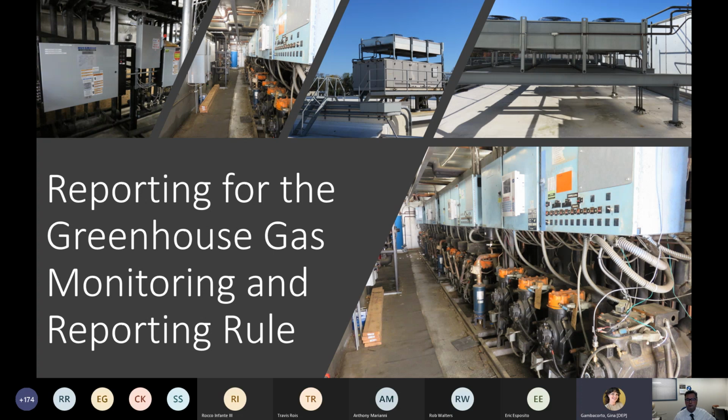Okay, we have one question from Brian Desselfin. He says, our HVAC contractor informs me that our chiller is 46 pounds. Do we not have to register? So that has to include all the refrigerant that's in the system, including in the piping. So if that's the condition, 46 pounds is under the threshold, then you do not have to register. You do not have to report.